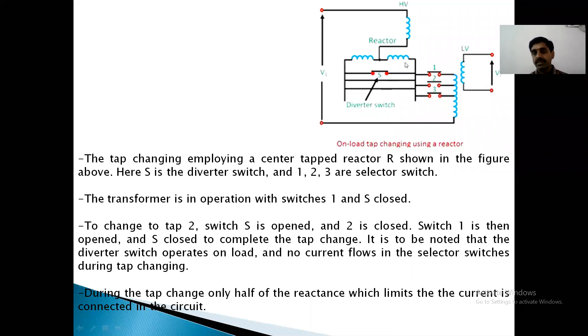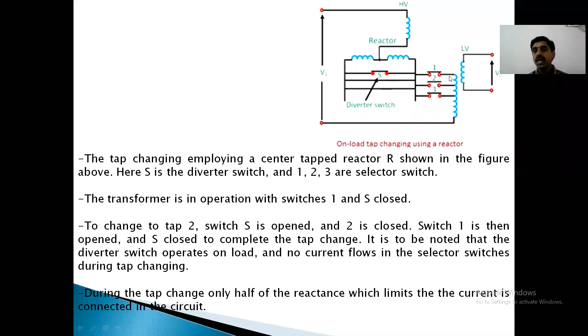The tap changing employs a center-tapped reactor as shown in the figure. Here S is a diverter switch, and 1, 2, 3 are selector switches. Initially the transformer is in operation with S and switch 1 closed — S1 closed — so the supply runs through S1 with the entire winding included. Now I want to select fewer turns, so the procedure is: open switch S, close switch 2, then open switch 1, then close switch S. Now the power supply is through S and 2.